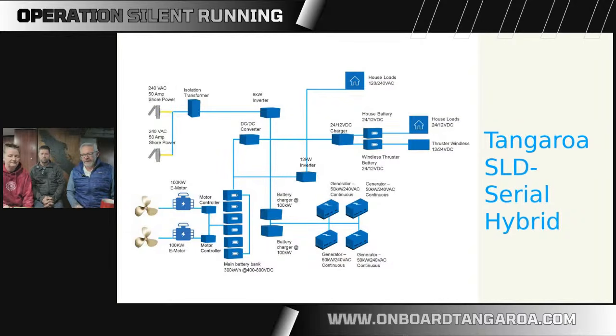So if you think about that in terms of annual impact, and let's just pretend they run 24/7 for 8,400 hours a year, instead of dealing with an 8,400 hour maintenance number, they're dealing with basically a 2,100 maintenance hour issue. So the cost of maintenance and service on the generators is spread out over a much longer range of time - it effectively is less per year than you would get if you had one engine or two engines running continuously.